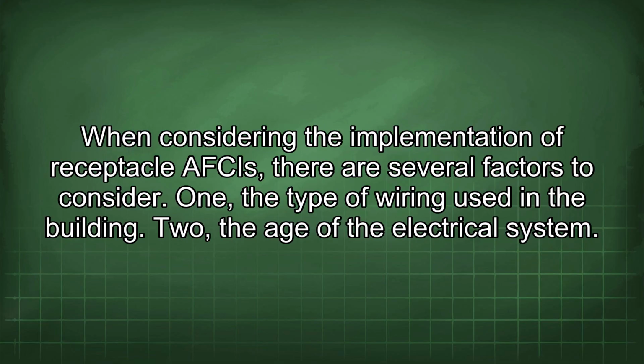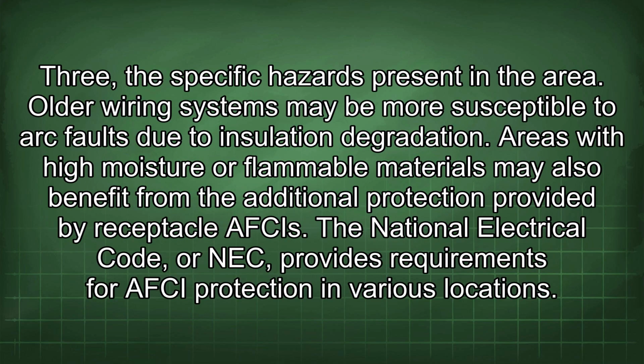1. The type of wiring used in the building. 2. The age of the electrical system. 3. The specific hazards present in the area. Older wiring systems may be more susceptible to arc faults due to insulation degradation. Areas with high moisture or flammable materials may also benefit from the additional protection provided by receptacle AFCIs.